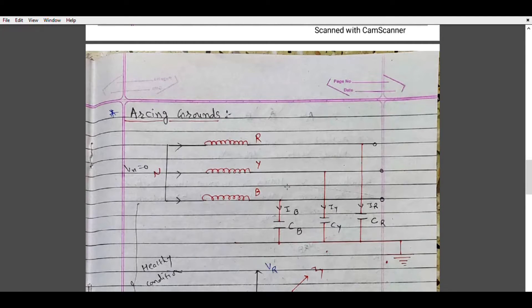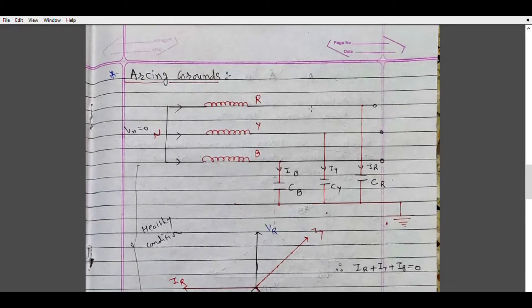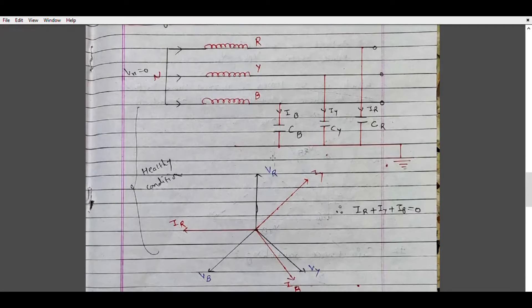This is the healthy condition, so there will be some charging current in the transmission line. The charging current flowing in the B phase is Ib, in the Y phase is Iy, and in the R phase is Ir. This is a balanced three-phase circuit, and that is why the voltages Vr, Vy, and Vb are displaced by 120 degrees with each other. The current Ir leads the voltage by 90 degrees because the charging current is capacitive in nature.